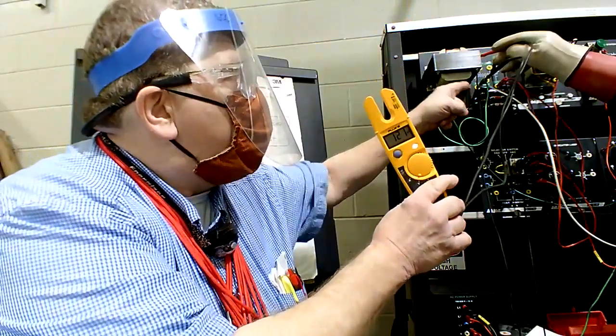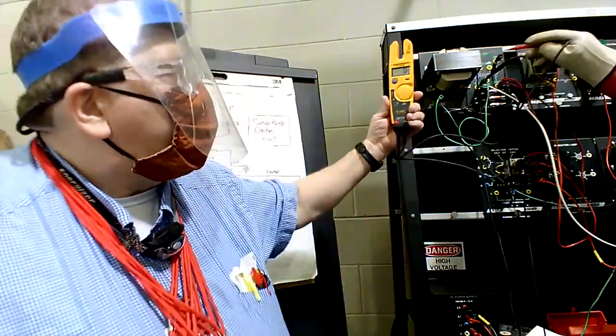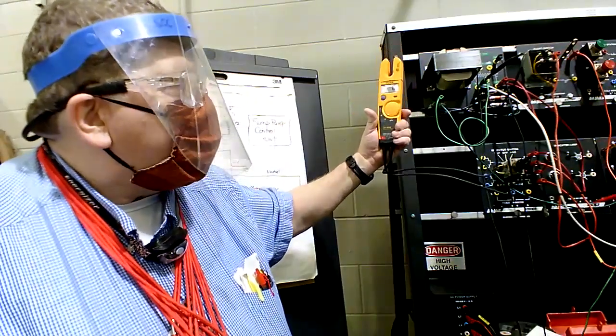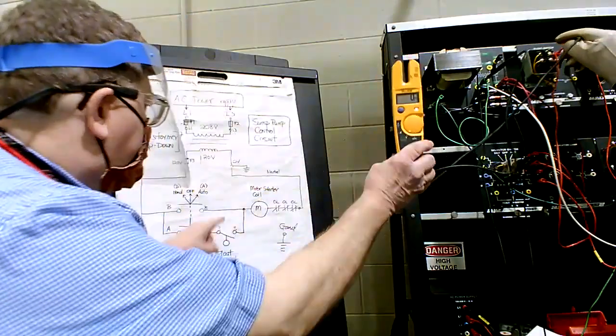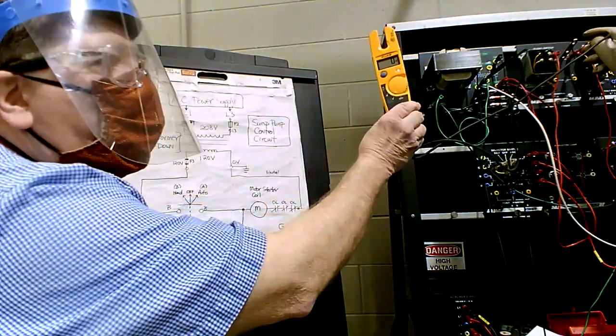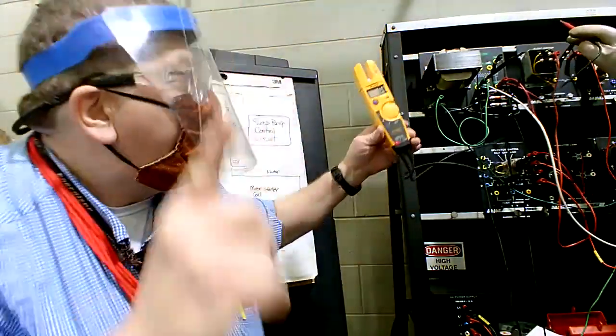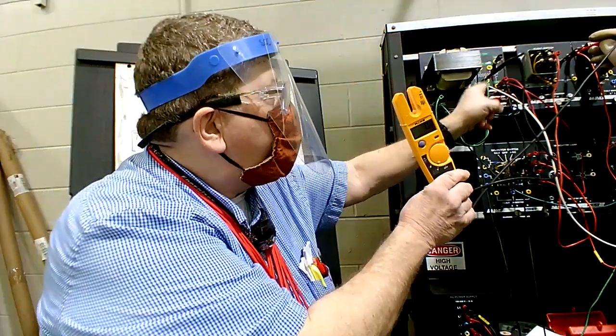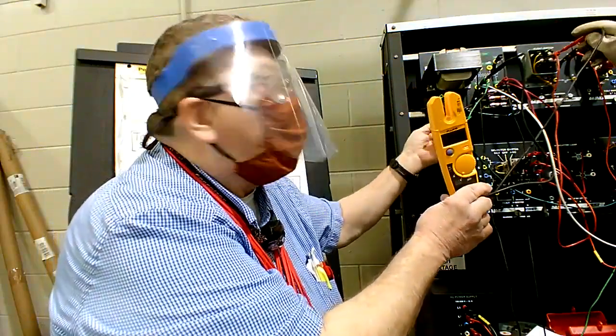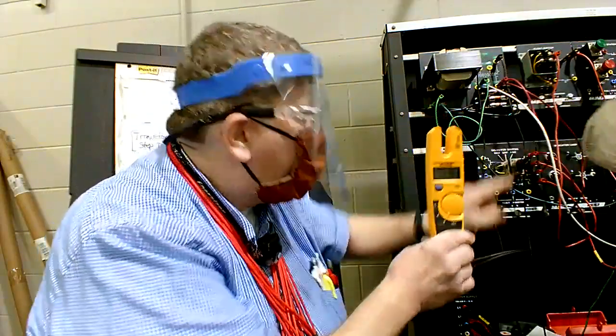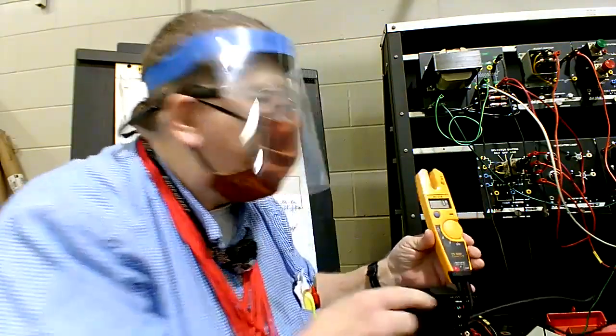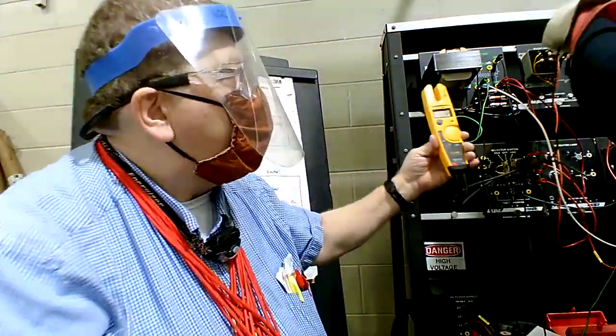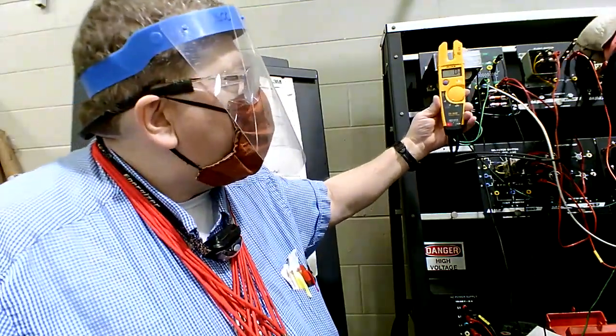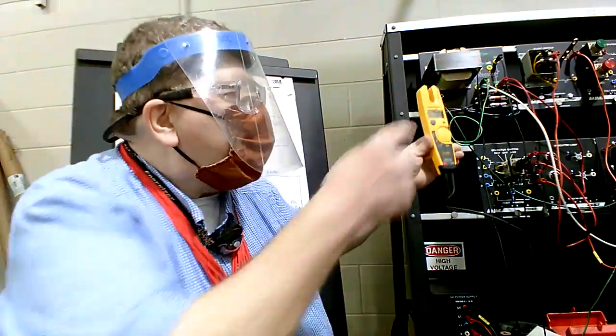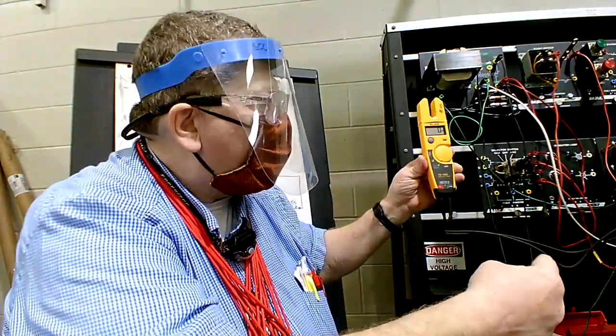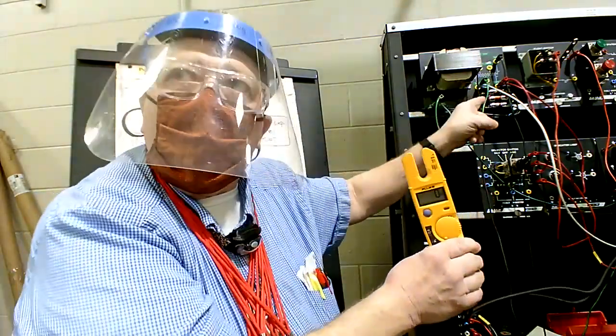Now look, he's got one probe on ground, and he's checking his voltage going into the float. He's getting 120 volts. He's got 120 volts leaving the float, and that's correct. He has his common on the meter over here on neutral and ground, which are together. Now move to some other grounded point. He's putting his reference point on a different grounding point and checking the float coming in and out. Look, 120 volts. He was able to go to some other grounded point with his reference probe and still get a good reading, as long as neutral is grounded.